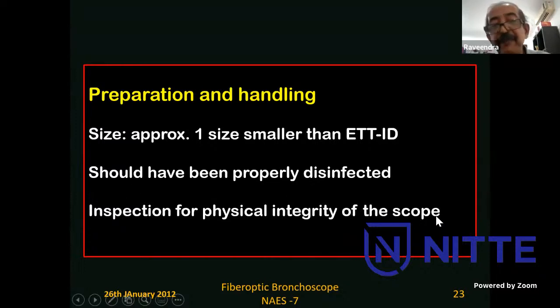Then inspect for physical integrity, and when you inspect for disinfection, see whether there is any physical impurities stuck to the scope, some protein, some material, secretions, etc. And for the physical integrity, you do a suction. There's a pressure gauge, especially for the fiber optic scope. It is not very important in the modern scopes. You can pressurize that and see whether there's a leak.